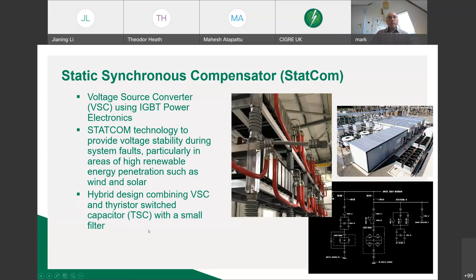So you can supplement it by using thyristor switched capacitors. The diagram on the right shows our layouts that we've installed in the last couple of years on the south coast to support the voltage stability challenges that we have down there. What these typically involve are smaller harmonics, which can generally be managed within the inverter.